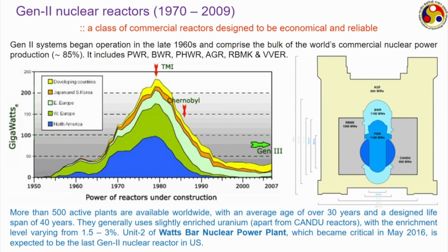So, they are still used, and also the high temperature gas that we are getting from these gas cooled reactors can directly be taken to a gas turbine, thereby avoiding any condenser kind of equipment. So, the plant becomes a bit simplified and gas turbines generally have very high efficiency.